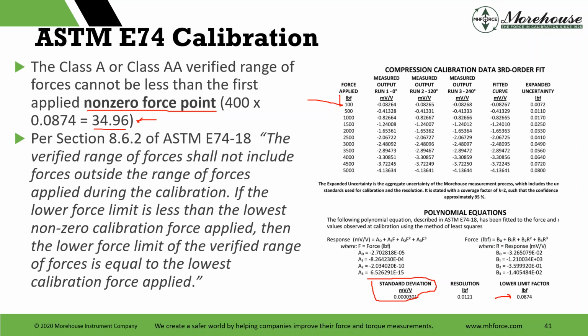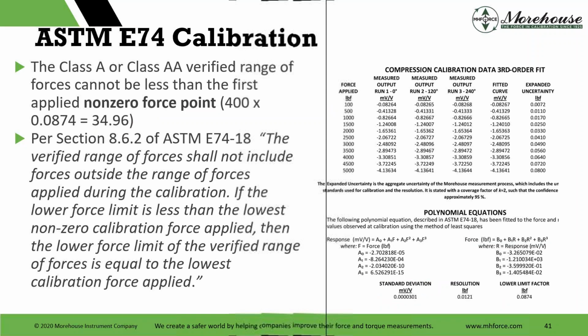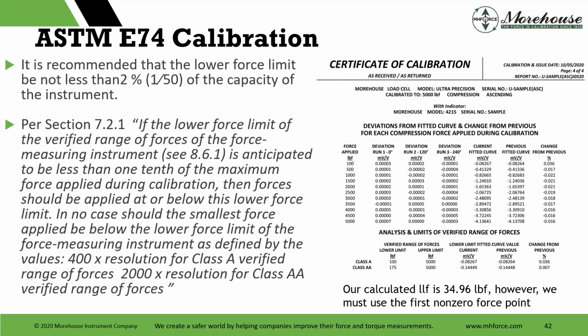So really, we see people violate this section 8.6.2 all the time. They report lower limits less than the first non-zero force point. It is wrong. It is not correct. And the calibration below that is not valid. So here, it's recommended that the lower force limit not be less than 2%, 1/50 of capacity per the instrument. So that's a recommendation. Unless someone tells us, hey, I want you to do a 1% point, I want you to go lower, we're going to follow the recommended guidelines.